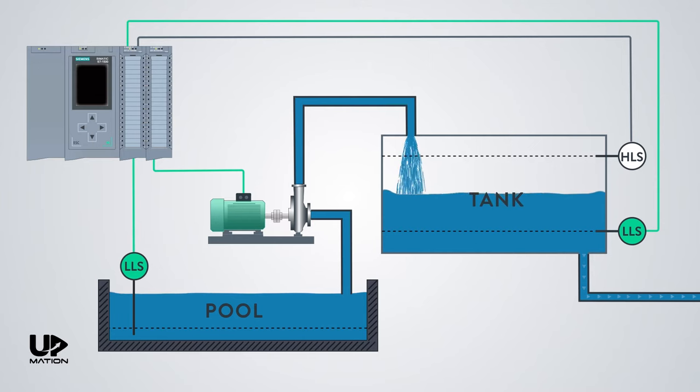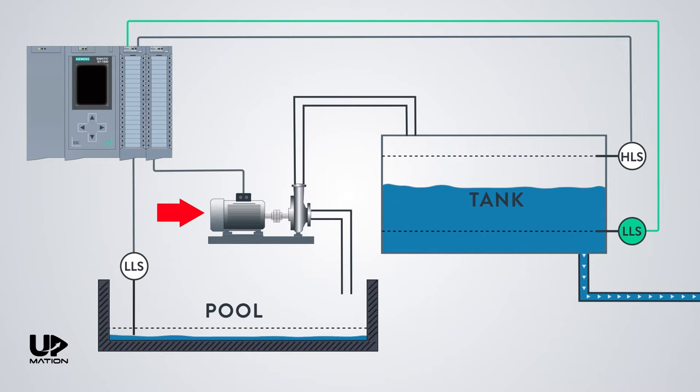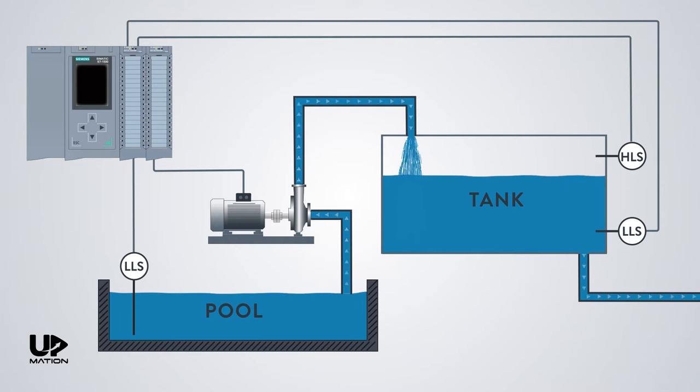There is also one other situation that PLC will shut down the pump. This would be when there is no water in the pool and its low-level switch does not sense any water. So in this example, we have three inputs which come from the level switches and just one single output which turns on and off a three-phase electric motor that drives the pump.